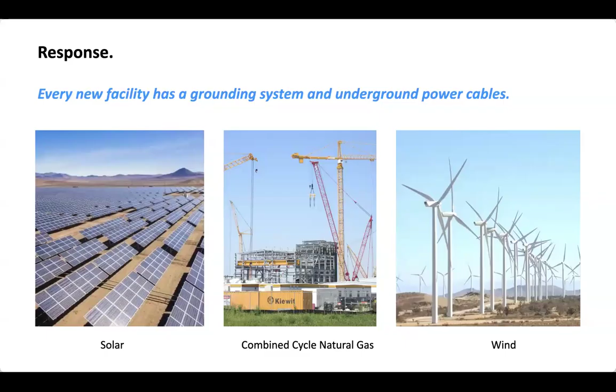The most productive farm acreage on the planet is going into solar farms here in the San Joaquin Valley. There's combined cycle natural gas, which is still conventional power plants, the new conventional power plants, which are quite efficient, and then wind. Of course, the combined cycles still have a carbon problem associated with them. So for my part, every new facility has a grounding system and underground power cables, and that's kind of where I come in. I measure the earth resistivity for grounding grid design, and I measure soil thermal properties for buried cable design.